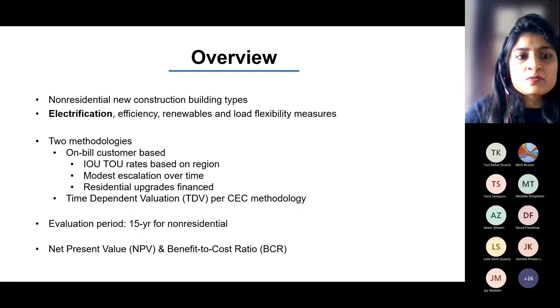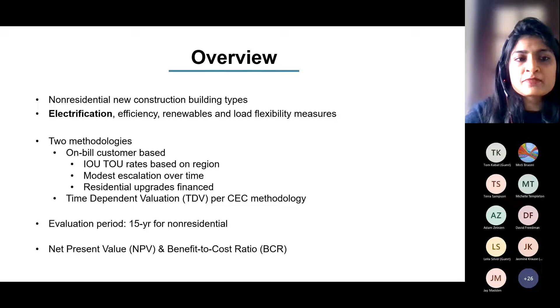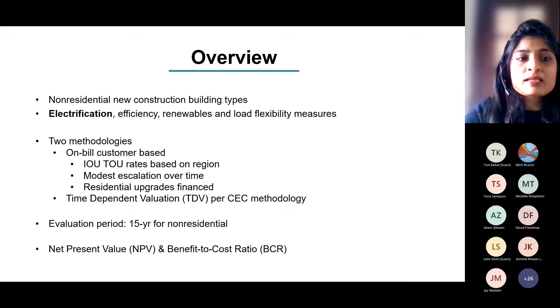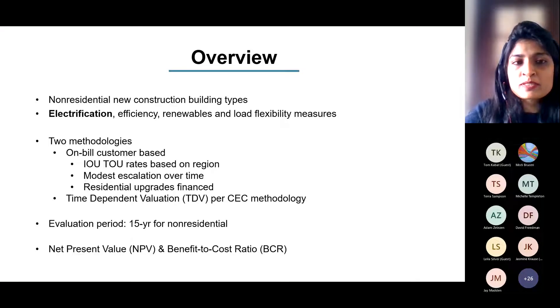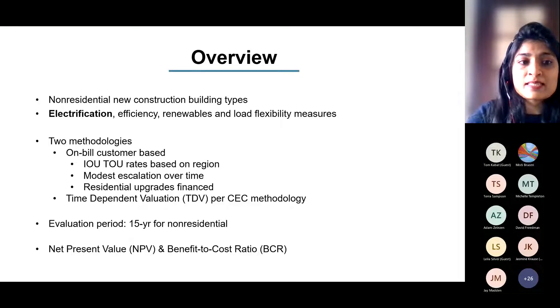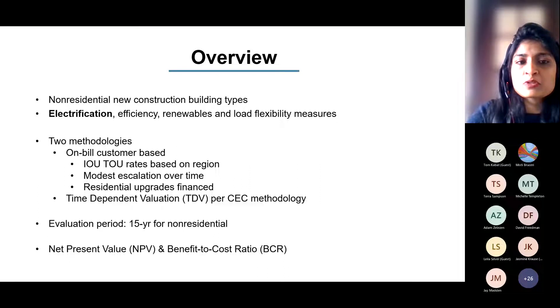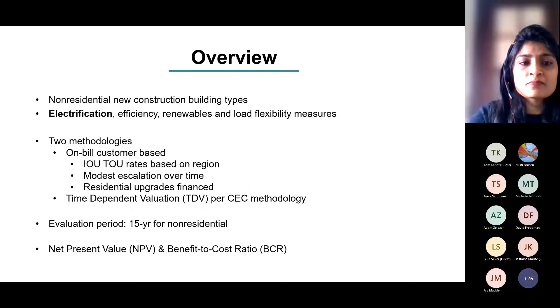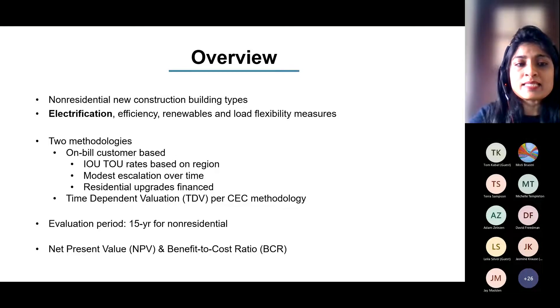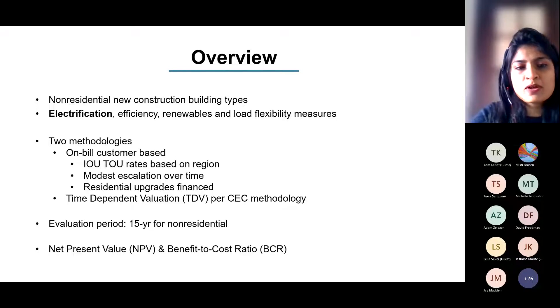Just a quick overview. We have new construction non-residential building types. The scope of the measures include electrification, efficiency, renewables, and load flexibility. We are evaluating cost-effectiveness based on two methodologies: on-bill — how much utility bill savings customers get over a lifecycle — and TDV basis, the CEC approach. We are using a 15-year life cycle for non-residential buildings. The two metrics are net present value (NPV) and benefit-to-cost ratio (BCR).